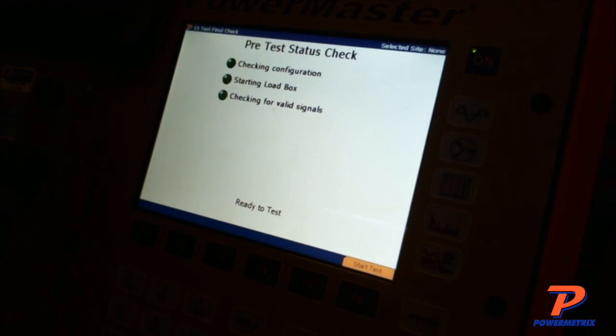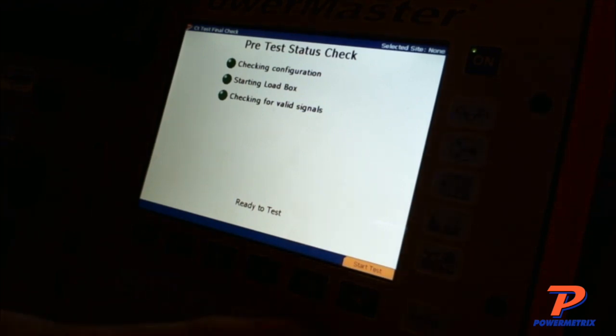If you did happen to have a medium voltage rack, the instance I remember up in Ohio, they had taken a lightning shot to a medium voltage rack. They were going to throw everything away, and I said hold on a minute. I benchtop tested all the CTs and they were dead on. So they grabbed some tools and went to take them off and restock them. You can do it, but remember, it's only a benchtop test, because all you're dealing with is current there, not voltage. All right, so I'm going to hit start test.